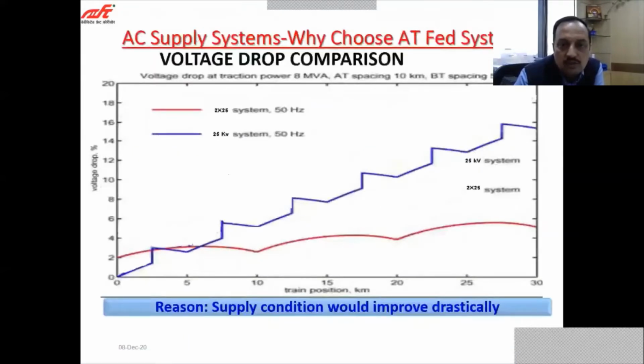As I show the voltage drop comparison here, in the case of IR, where the 25 kV system is followed, as we move away from the traction substation the voltage drop increases in an almost linear fashion. Whereas in the 2 into 25 system, we see that a curve is followed for the voltage drop. So for the same distance, the voltage drop in the 2 into 25 system is much less compared to this single 25 kV system. Because the voltage drop is less, we are able to increase the distance between the two substations on the DFCCIL system.